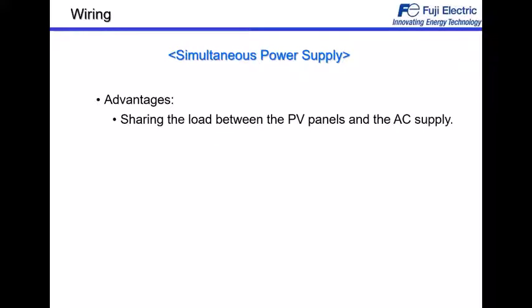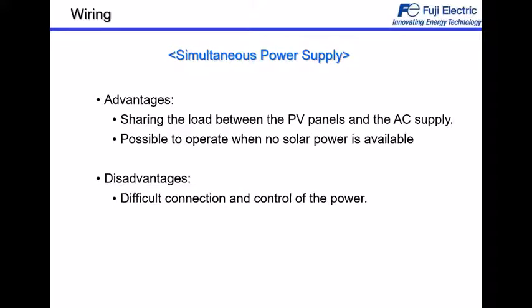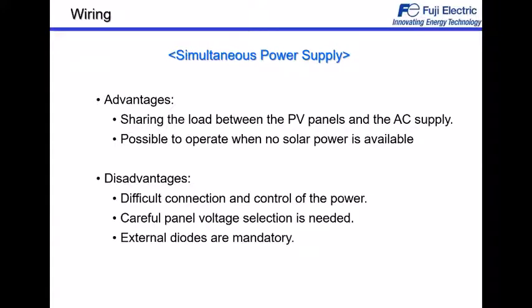Advantages: sharing the load between the panels and the AC supply. It's possible to operate when there is no solar power available, but it has some disadvantages as well. The connection is difficult and the control of the power is a bit more complicated. A careful panel voltage selection is needed. So here, since we have both the panel and the AC at the same time, we need to carefully select the voltage of the panels. So we need some engineering support here. And external diodes, in this case, are mandatory.